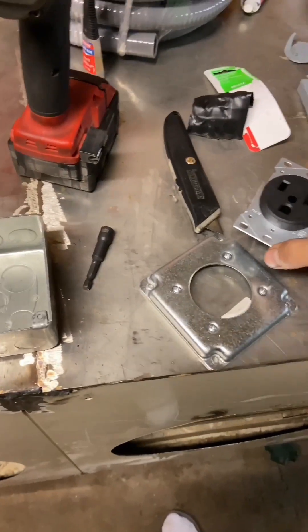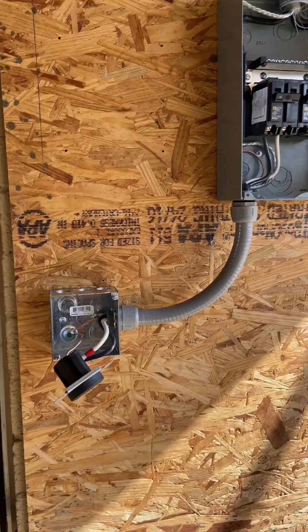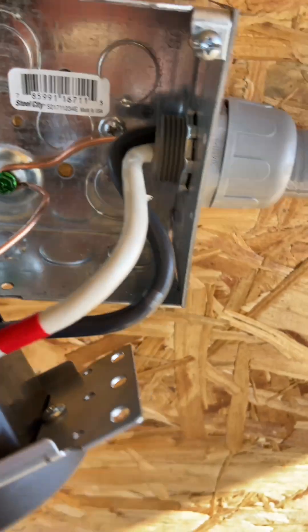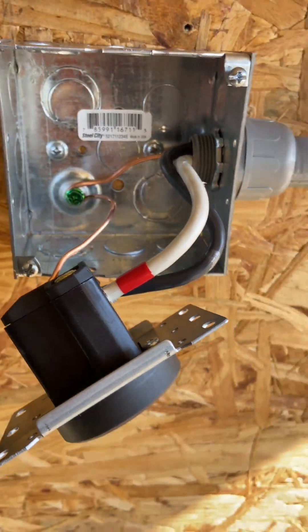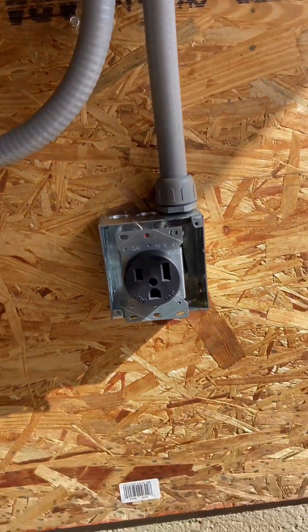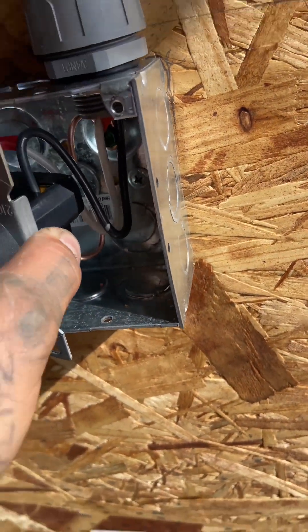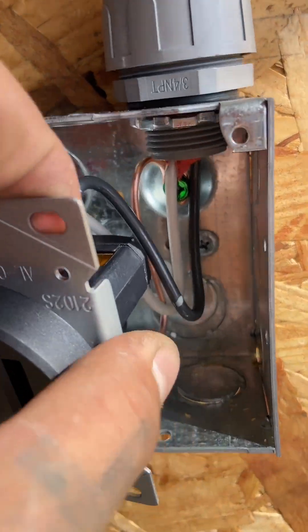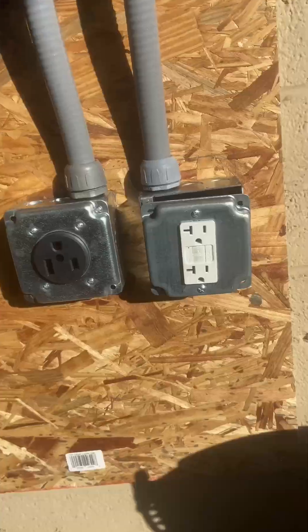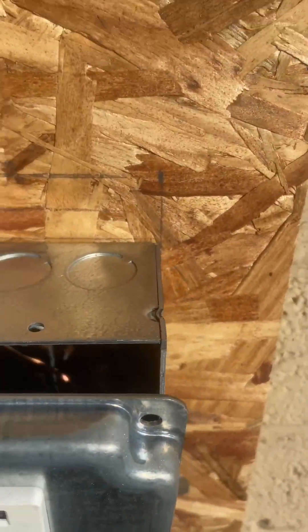Now we're going to be running the 50 amp receptacle for my welder. We got the ground screw and our two hots — number 6 wire. For the 30 amp breaker running on the 50 amp receptacle, I'm running number 10 wire with the two hots and a ground, grounded to the box too. We got the 20 amp installed too — 12-2 wire on this one with the green screw for ground.